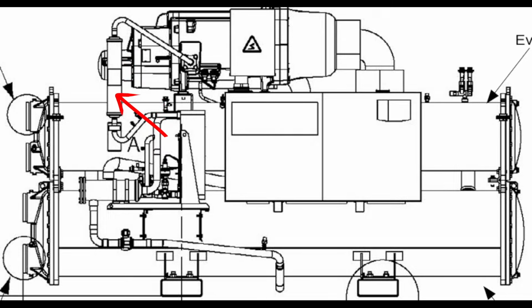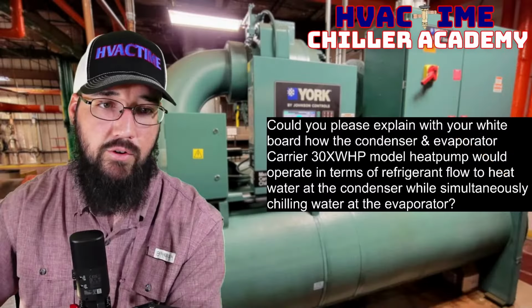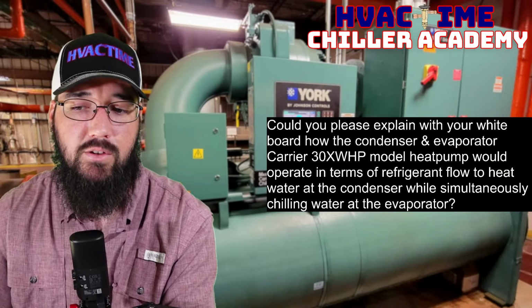Anyway, so yeah, we come through there, economizer port into the compressor. All that compresses, comes back out the discharge. That is our basic cycle here. We have a standard, call it water-cooled condenser with our discharge lines coming in. We have a flooded evaporator.